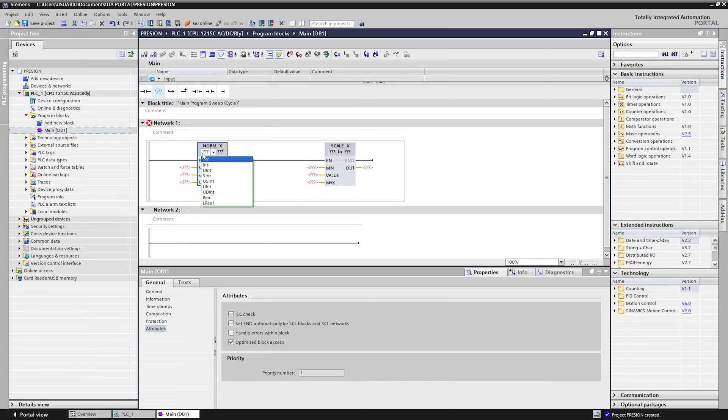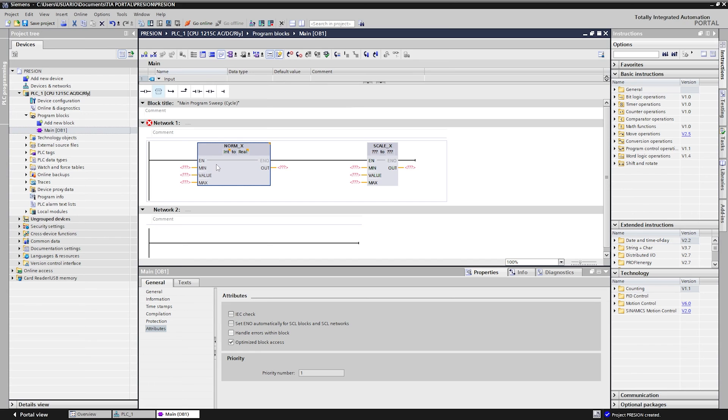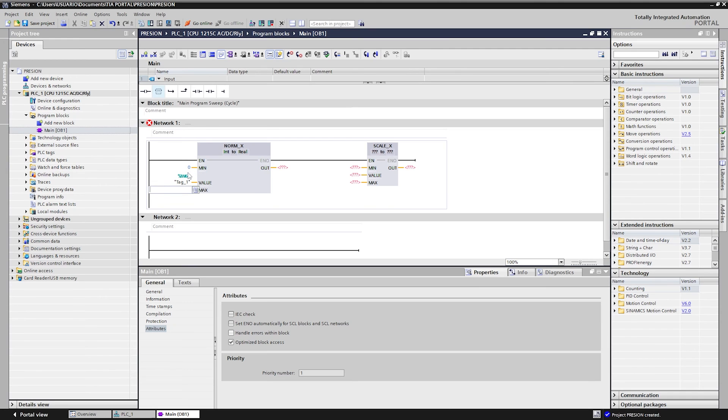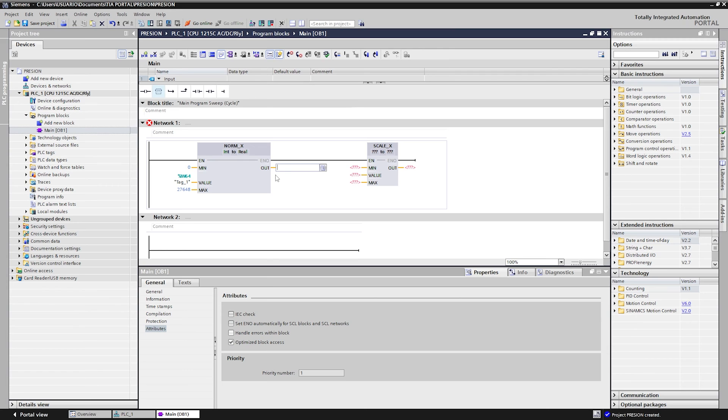In the norm block we convert INT data to real. In min we put 0. In value the address IW64. At max, 27648, which is equivalent to 10 volts. In out we use an MD0 memory.